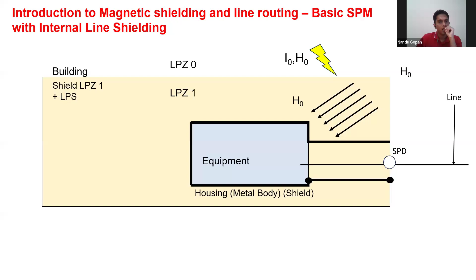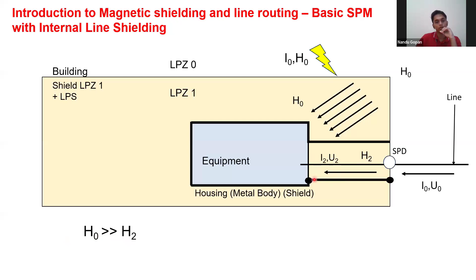This is a mistake. If there is a lightning strike on this structure, the same magnetic field strength outside will be reflected inside the structure if you have not done good shielding, such as using a brick wall. But look at the power line coming in. If this power line uses internal shielded wires and you have terminated the shielding here, there will be a reduction of H0 to H2 inside this shielded area. So H0 will be so much higher than H2. And if there is a good SPD, you will also reduce the surge to the equipment, like in this example.